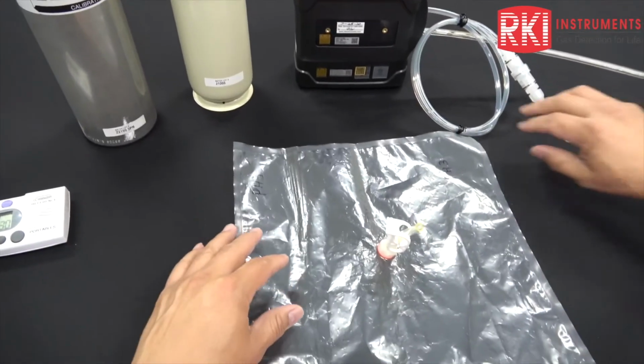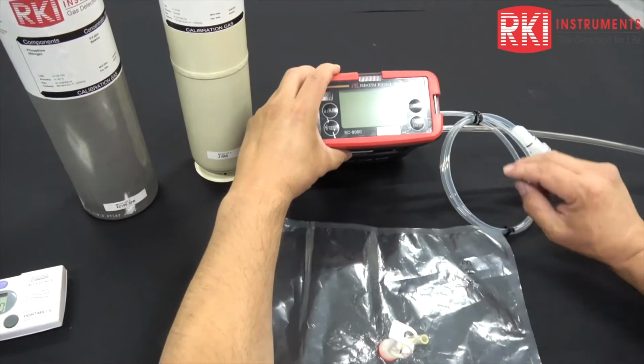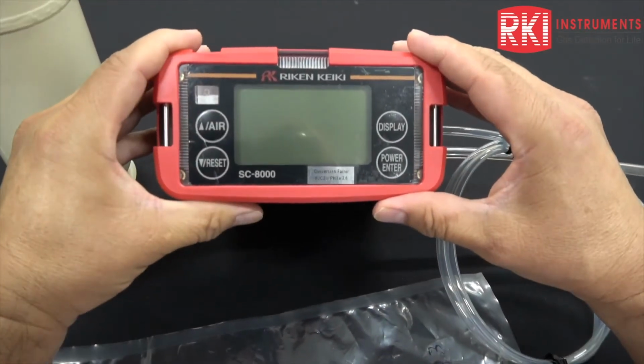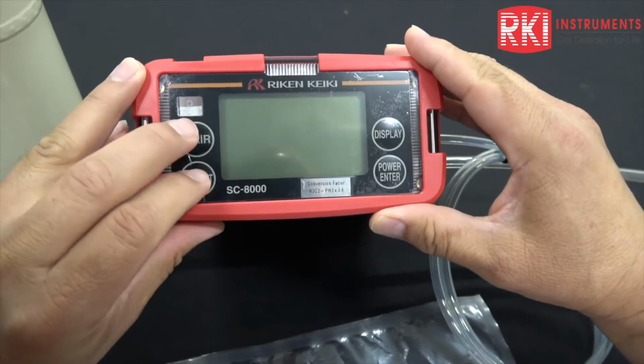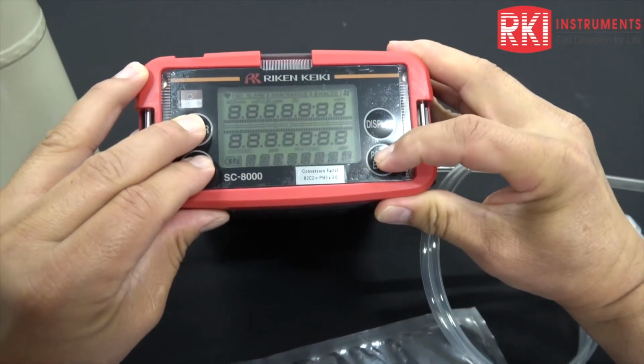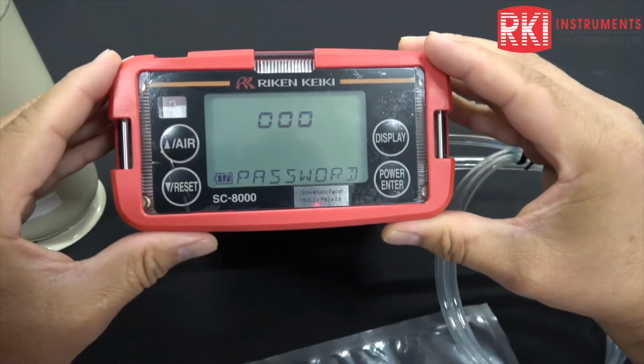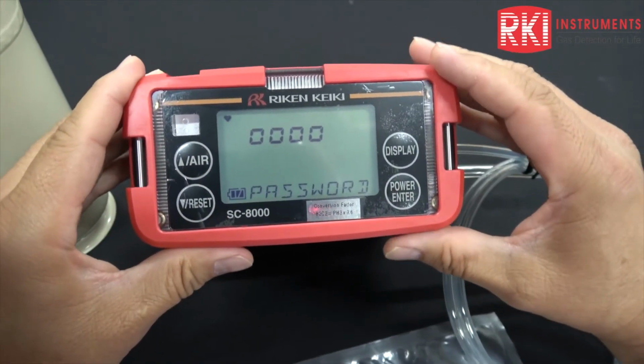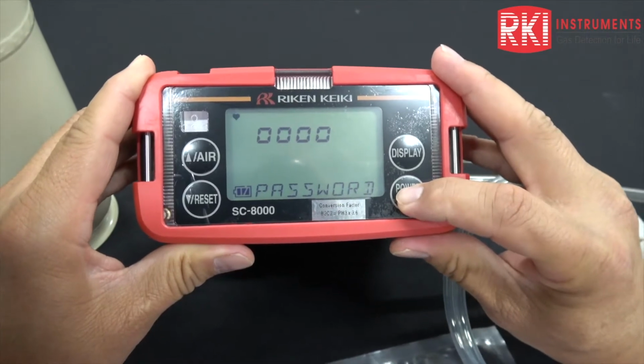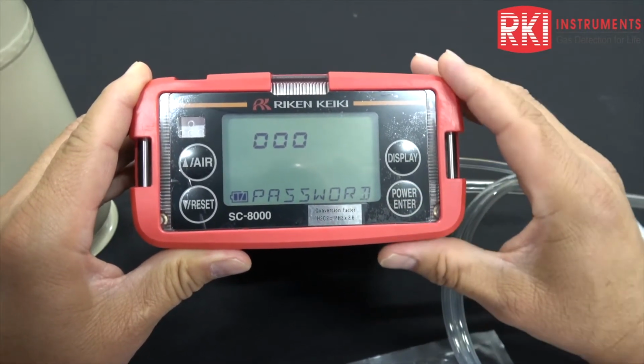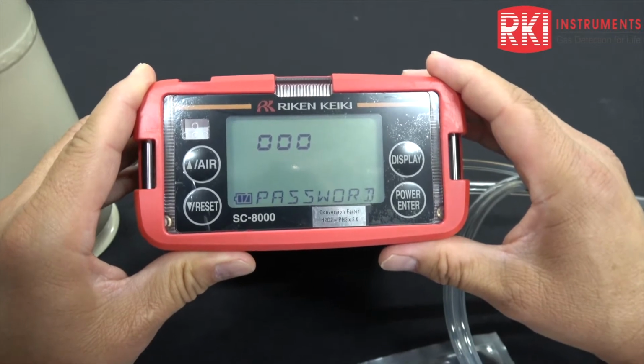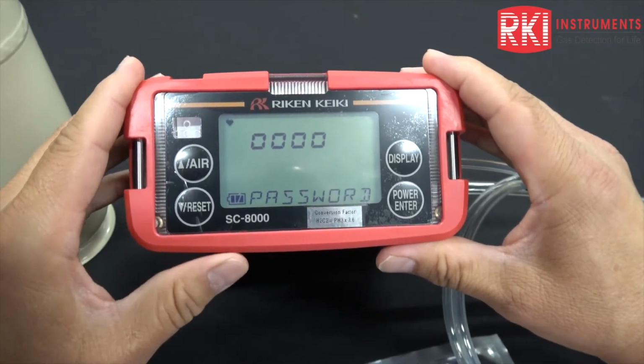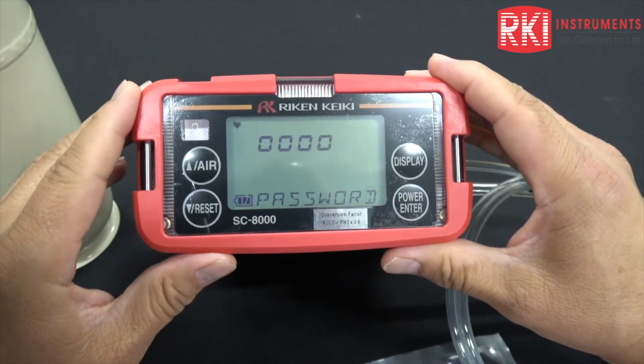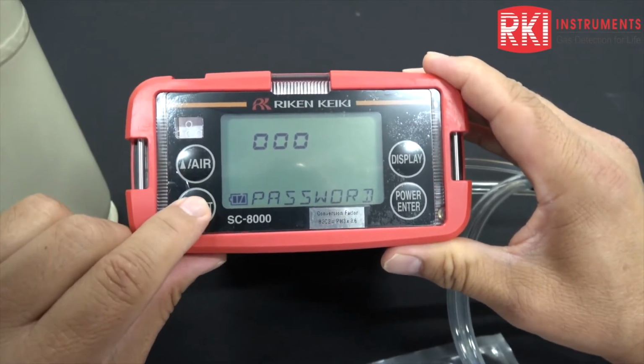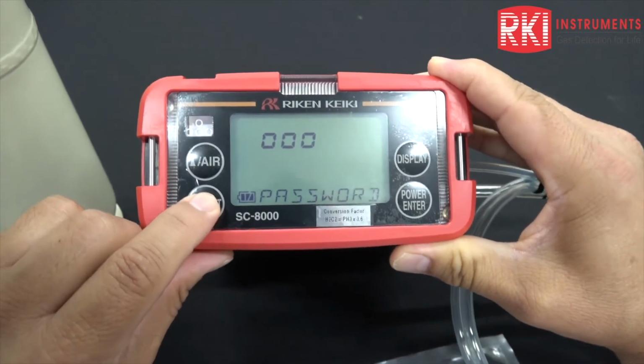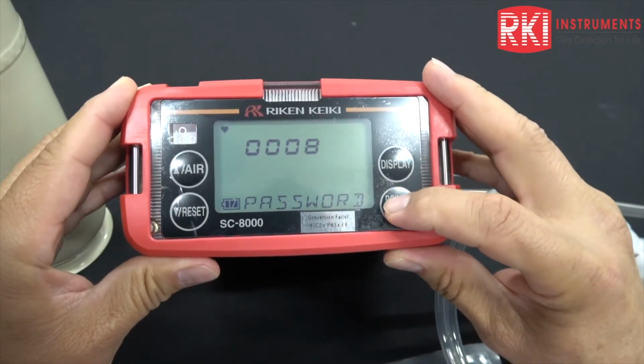So first of all, I'm going to put the unit into a calibration mode, and we'll start from the off position, and we'll press the air and reset buttons together, press and hold down the power enter button, let go of all three when we hear a beep. Then it's going to ask for a password, and then I'm just going to press the enter button to navigate the cursor over to the far right, and then the password is 0008. So basically, most of our passwords for our units are a model number backwards. Then the quickest way to get to 8 is just use the down arrow key. It'll drop down to 9 and then 8. And then press the power enter.